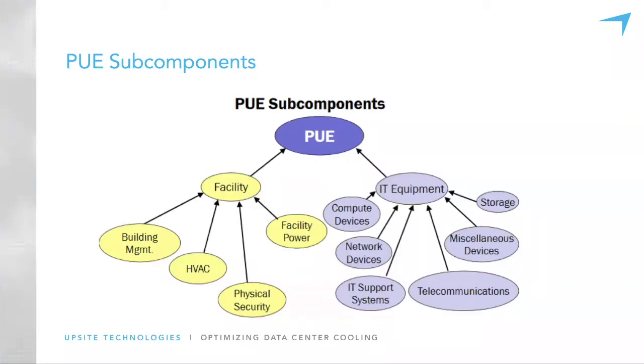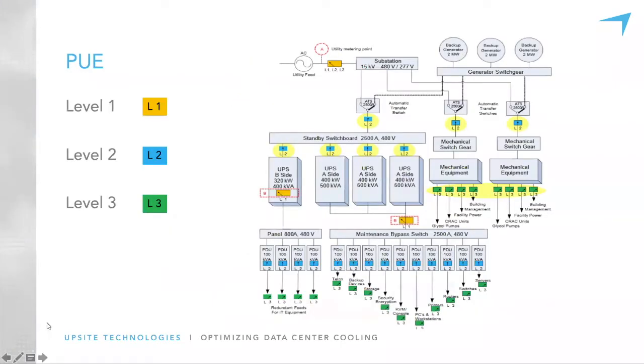So again, I was confused trying to decide what went where, but consistency is key. If I, by some chance, counted equipment that should have been part of IT equipment in with the facility, but measured it exactly the same way every time, I at least have consistency. Later, if I find out something should have been with IT equipment and not facility, it's okay to make that correction, but just be consistent with how you're measuring PUE to be most effective in managing your facility.